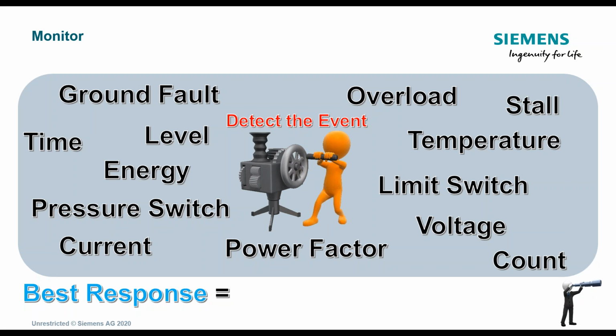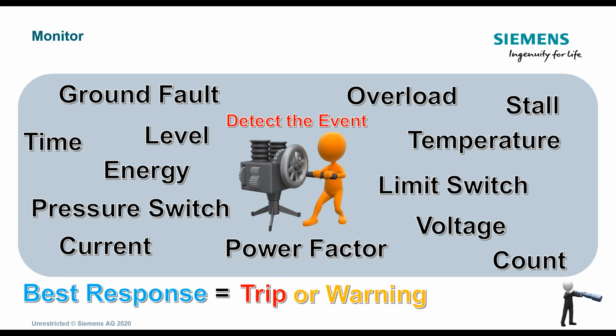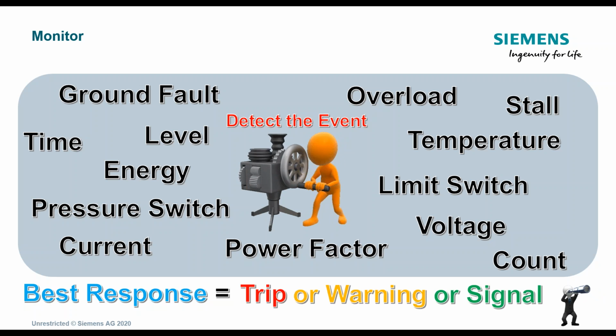Okay, so best response equals a trip or warning or a signal. With the remote I/O in the field, with the SIMOCODE we can classify how we want that motor management to act and react to events. We can trip the motor, stop the entire process, or we can send a warning to the operator and say, hey, we have a problem in the field, it's approaching a certain level and so forth. Or we can just signal the operator to say, please, when you have a minute, take a look at this and find out if this is okay. Or, hey, we're just letting you know everything's all as well.